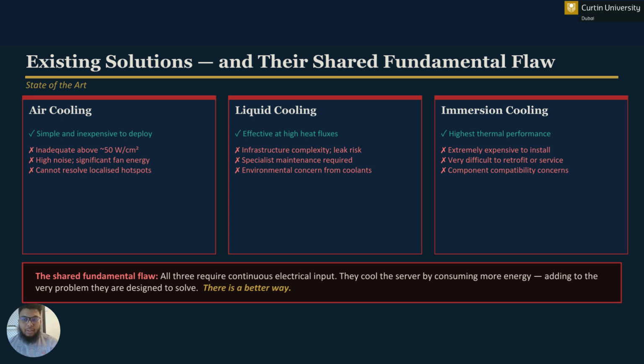The industry has responded to this challenge with increasingly sophisticated active cooling systems. The three methods most commonly used are air cooling, which is fundamentally constrained by the low volumetric heat capacity of air and becomes inadequate above approximately 50 watts per square centimeter. Liquid cooling offers substantially greater performance but introduces infrastructure complexity, leak risk, and requires mandatory specialist maintenance. And lastly, immersion cooling, in which servers are submerged into dielectric fluid, represents the current performance frontier but remains prohibitively expensive to install, difficult to retrofit, and is problematic for long term component compatibility.